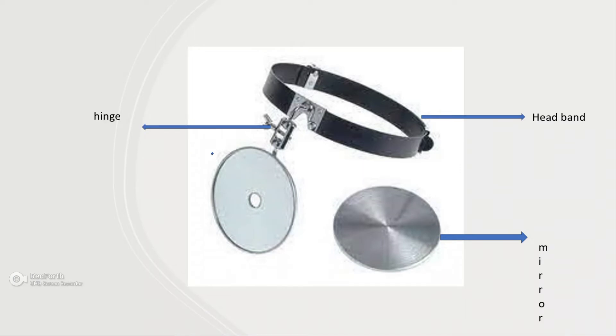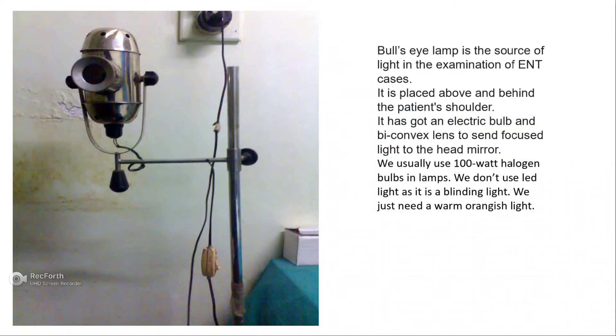With the head mirror, you have to manually adjust everything, which can be troublesome. The bull's eye lamp is the light source for examination. Light from it is converged by the concave mirror. The lamp is placed above and behind the patient's shoulder. It has an electric bulb and a bi-convex lens. We use 100-watt halogen bulbs — not LED — because LED is very blinding and too sharp to properly focus.